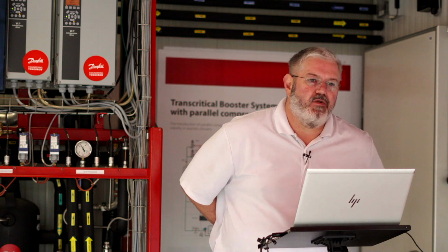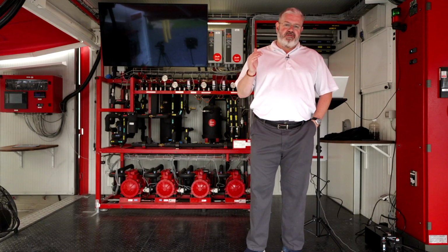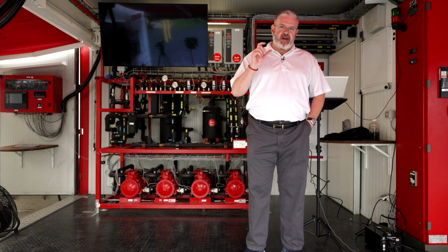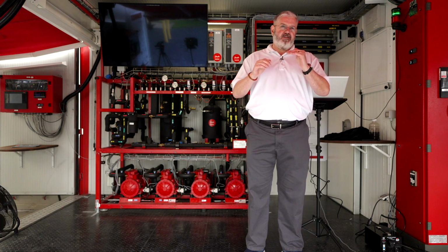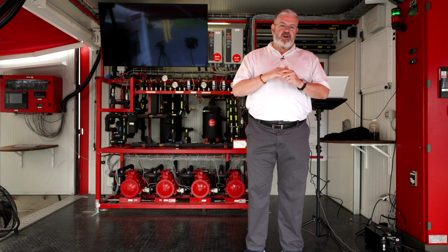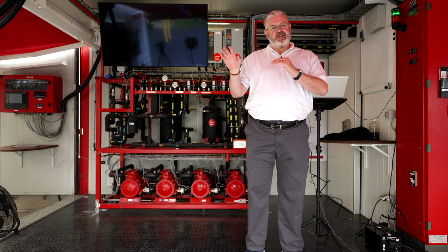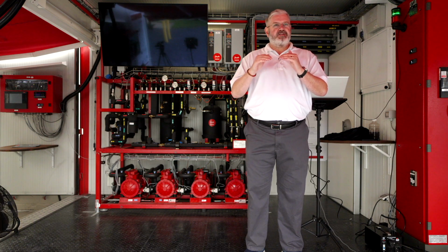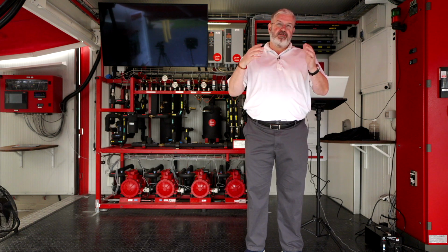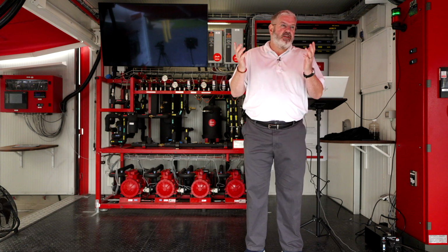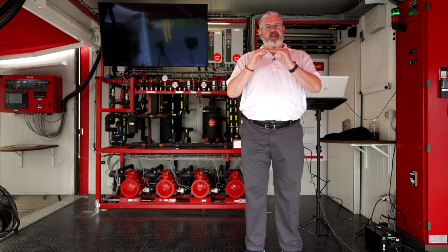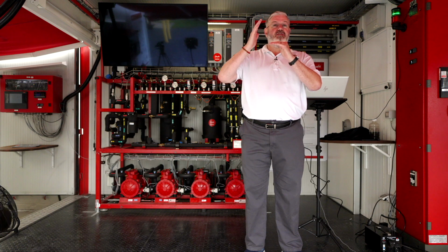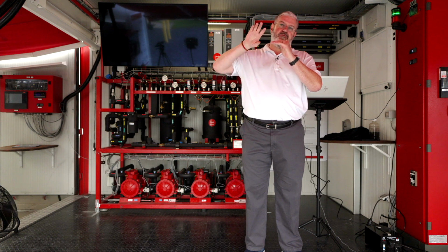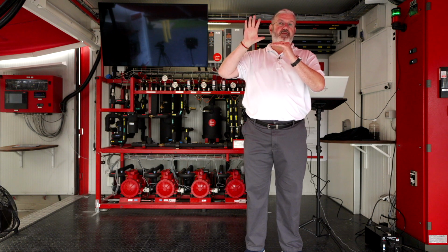So we have a question. How would a CO2 system work in sub-zero ambient temperatures? I got that one yesterday. It's a really good question. If you think back to when we talked about the high pressure valve, you give it a minimum range and a maximum range. So regardless of what temperatures the gas cooler is seeing, if you tell it the minimum is 600 pounds, whatever temperature that equates to, let's say that's 50 degrees-ish, if you set that as the minimum, it's going to close itself off to build the pressure in the gas cooler to not be below your minimum setting.